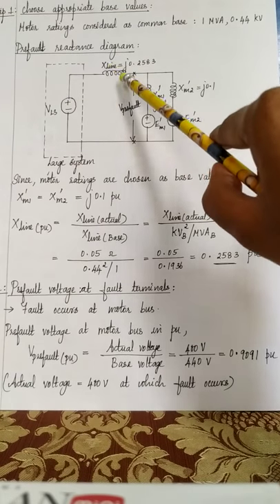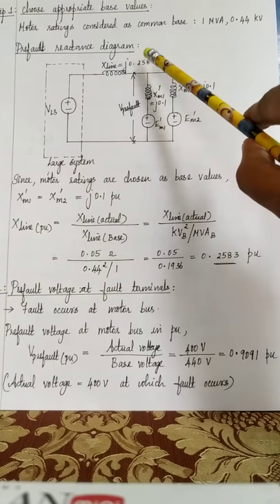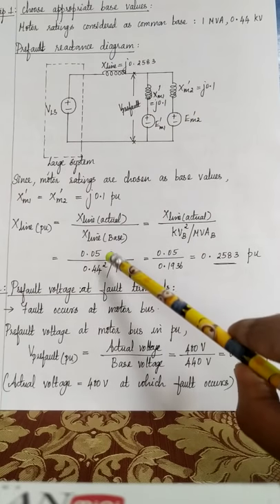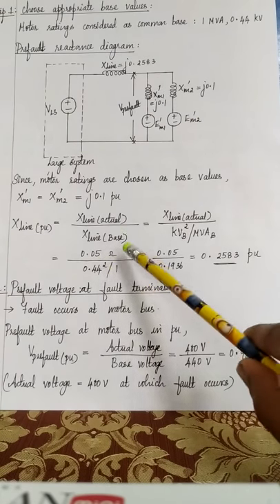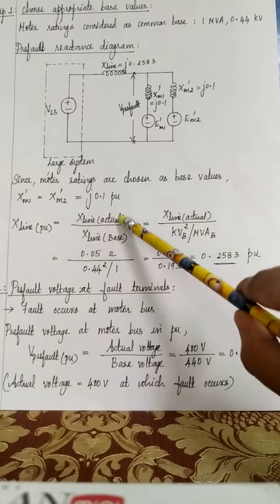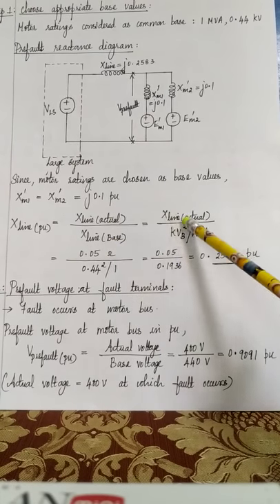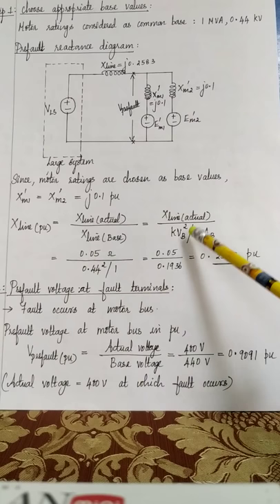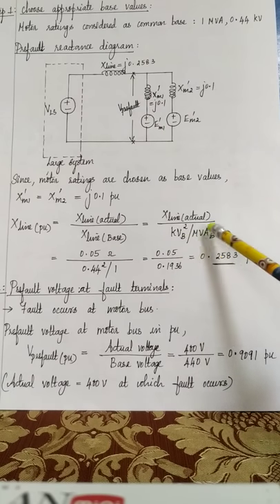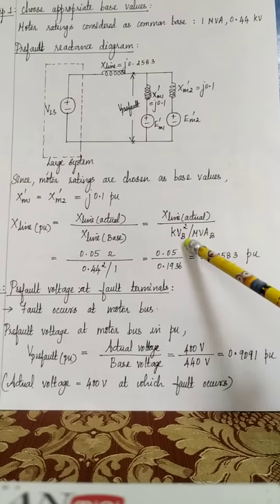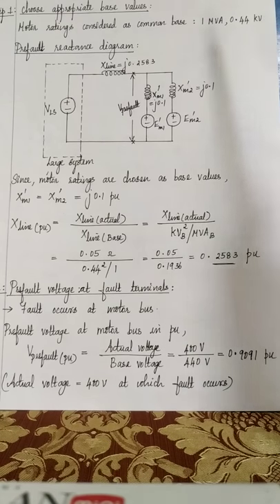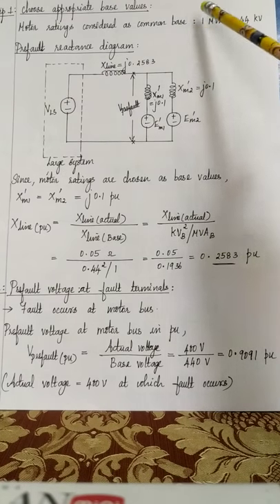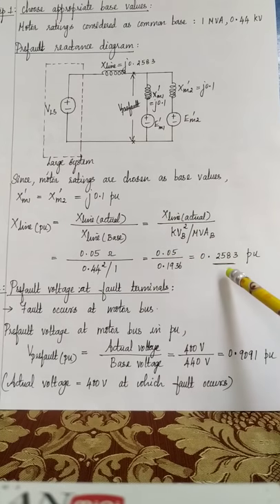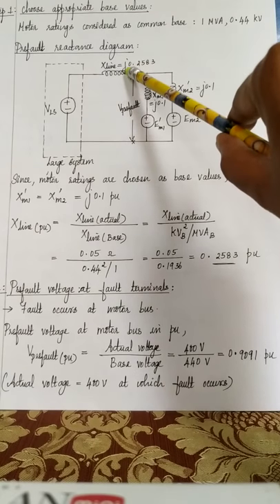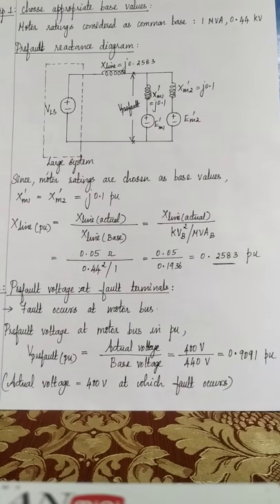Now the transmission line reactance is given as 0.05 ohm. We have to convert that to per unit using the formula X line actual by X line base. X line actual is 0.05 ohm. X line base is KVB square by MVAB. KVB square is 0.44 square, and MVAB is 1. On substituting, you will get X line per unit as j0.2583 per unit.